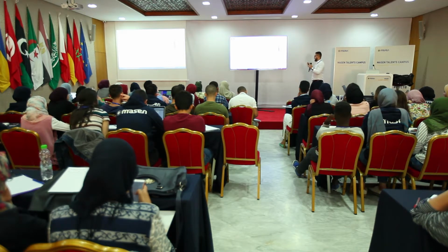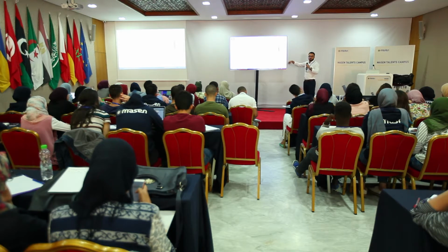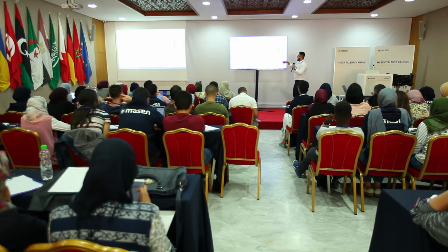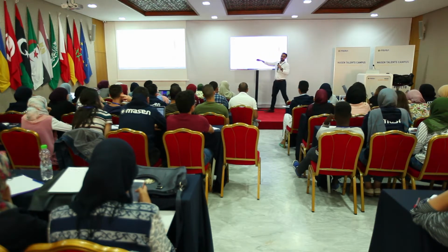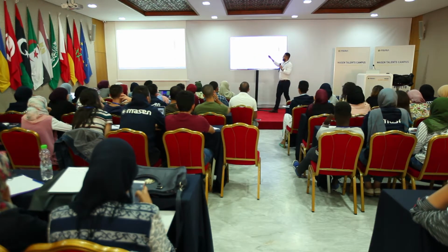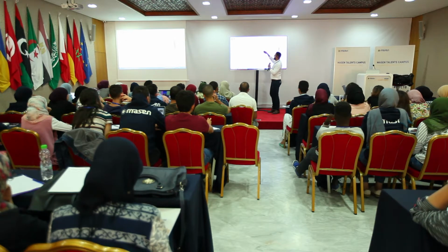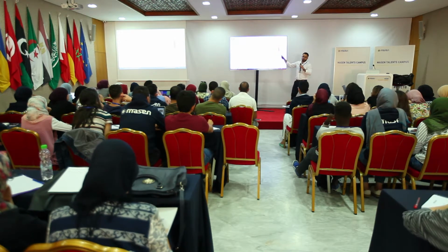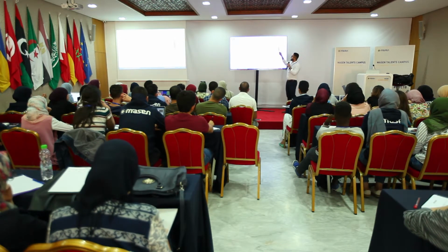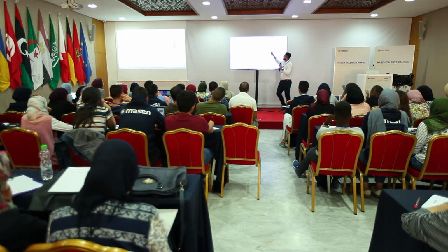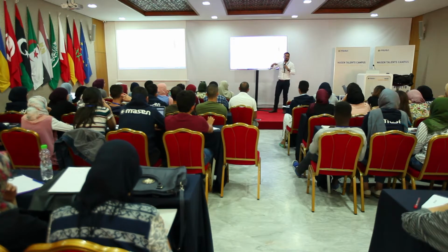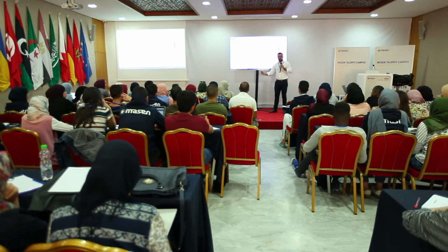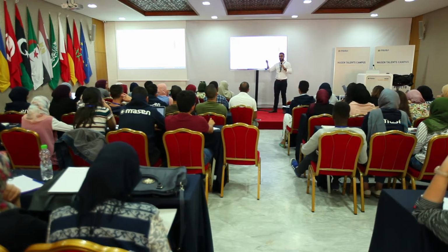So you see that every day, in this week of operation, what they did, I was not there, is basically every day the plant gets full. You see that sometimes it's actually full, like a plateau. And then discharge, and then full, and then discharge, and then full, and then discharge. So this plant is clearly designed for a base load operation, like continuous operation. And in this week, it actually managed to do it, and the red line then is the actual power.